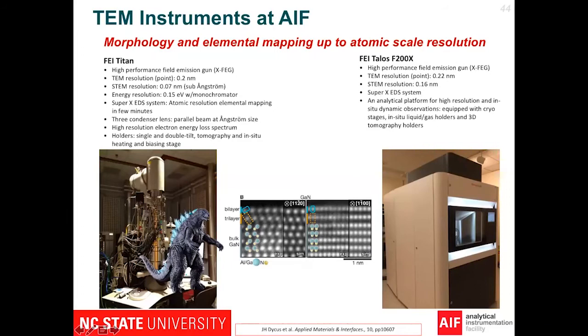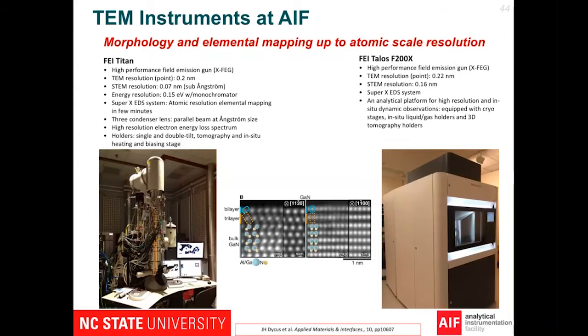We don't create monsters with those electrons — we funnel them to our two TEMs, which I call Ferrari TEMs: they're extremely high-performance microscopes. We have the Titan, which has the highest spatial resolution of any of our TEMs. In terms of spatial resolution, we're not talking nanometers or even sub-nanometer — we are below an angstrom, down into the tens of picometers. In this case, technically 70 picometers of resolution, meaning we can resolve things that are about 70 to 80 picometers apart.